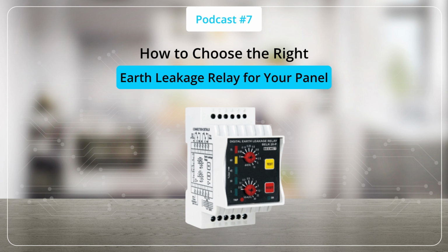Modern digital ELRs offer several advanced features that make them particularly useful in industrial environments. They can provide alarms before a complete shutdown occurs, allowing operators to take corrective action before a fault becomes critical. They are capable of working with different waveform types, including AC, pulsating DC, and smooth DC loads. Many digital ELRs support communication protocols, such as Modbus, making integration with PLC and SCADA systems easier. They also offer event logging capabilities, which support predictive maintenance by helping maintenance teams monitor system performance and fault history.